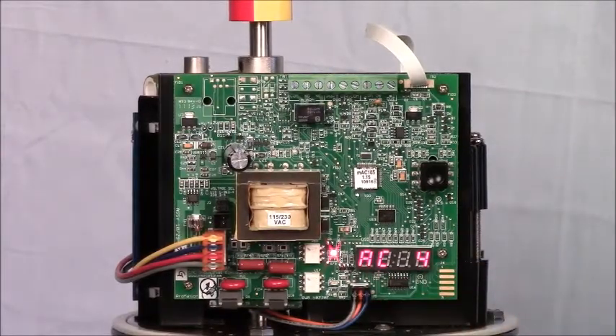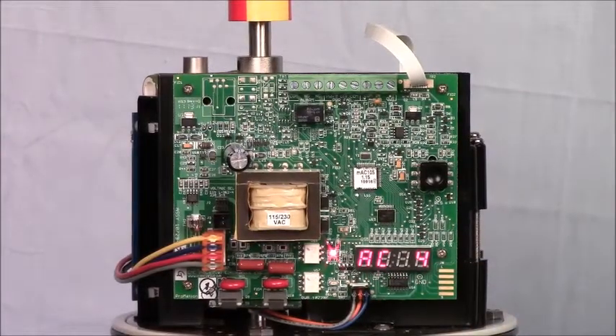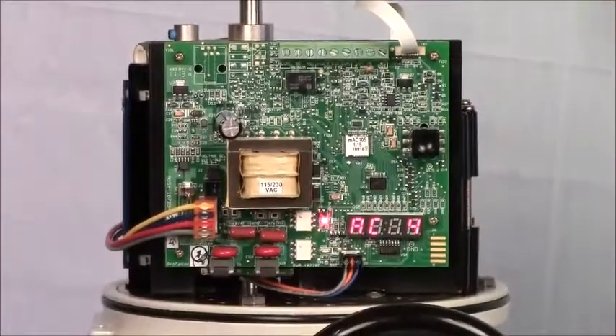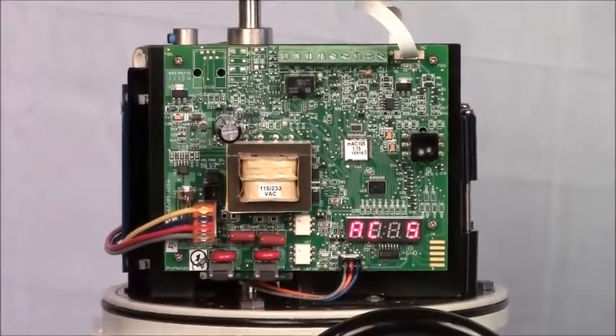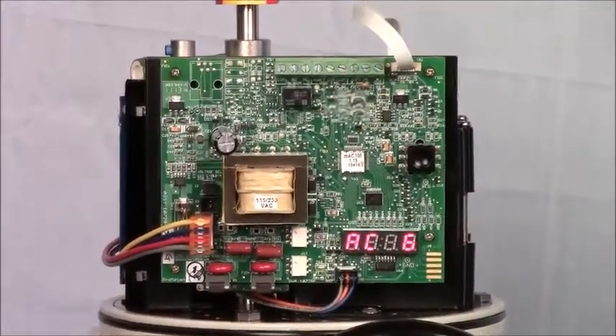Auto-cal 4, notice the actuator is moving. It first goes to its closed position, indicated by the red light, finds its closed position, opens up about a third of a degree, that sets the closed position.